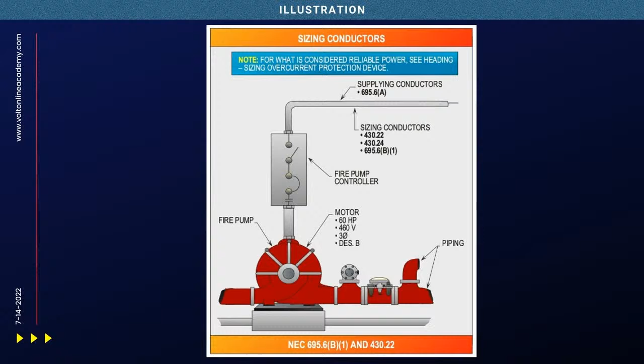Keep in mind, too, that with a lot of these fire pumps, there's really no PPE that you could use to work on them energized. So I just wanted to tie in that 70E reference: they're not likely to be worked on while energized because they don't have overcurrent protection devices that are sized for personnel protection. Right, they're sized to hold indefinitely. Absolutely. I always tell everybody, when you're sizing a motor, go over and look at 240.4(G), where you pick up your specific conductor application. It talks about when you're sizing motors to go look at Article 430, and it has all these parts to go look at.